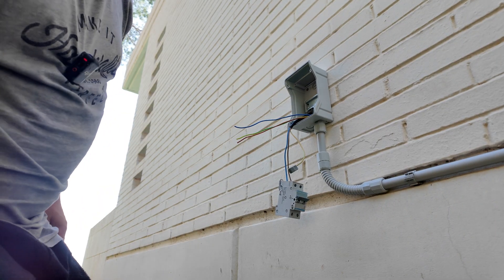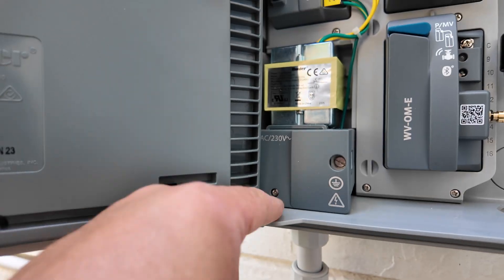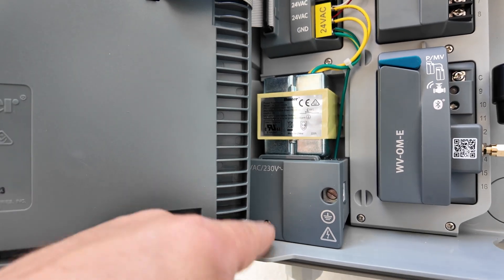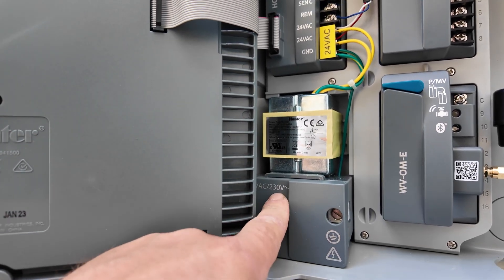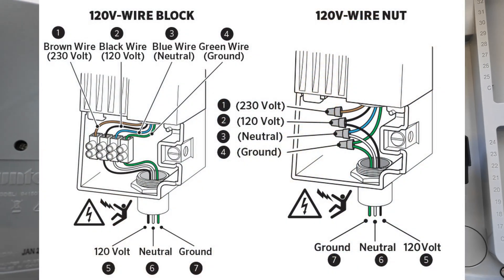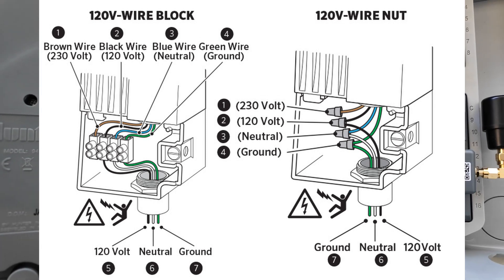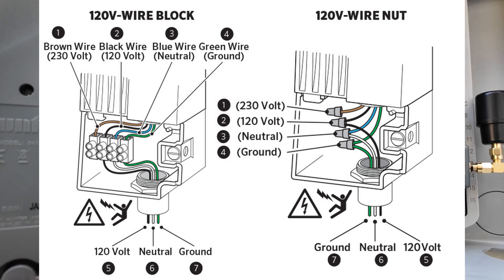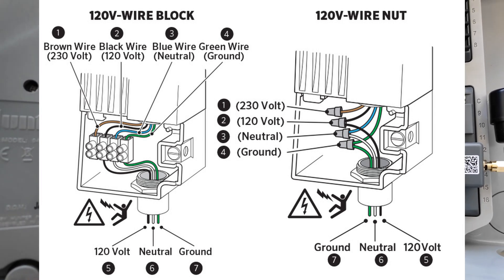A very important thing — in the box there are four cables instead of three. The brown cable is for European installation at 230 volts, and the black one is for 120 volts. Fortunately, Hunter did a good job and labeled each of the cables with which voltage they use. Make sure you read it and connect your cable to the desired voltage, regardless of the color.